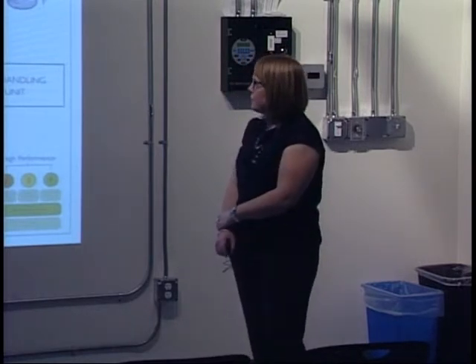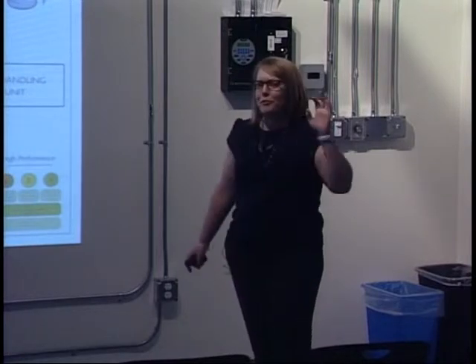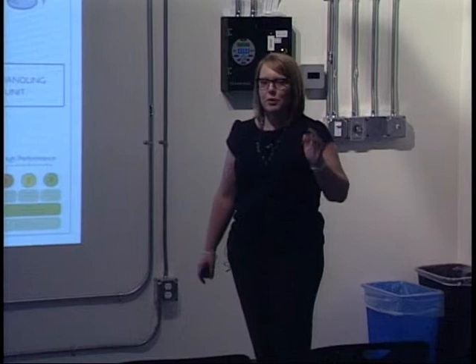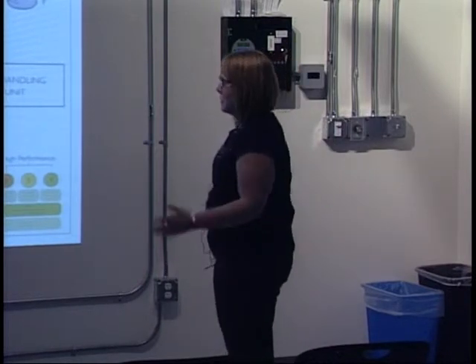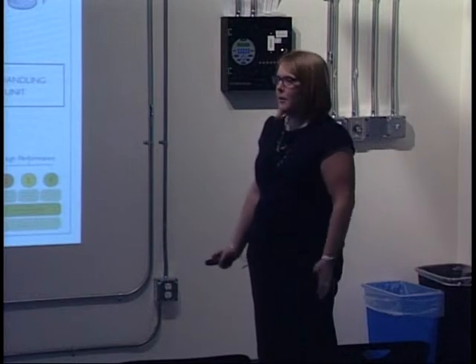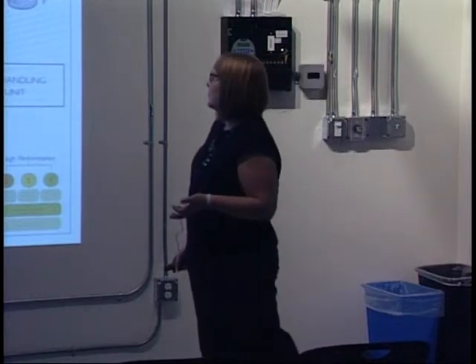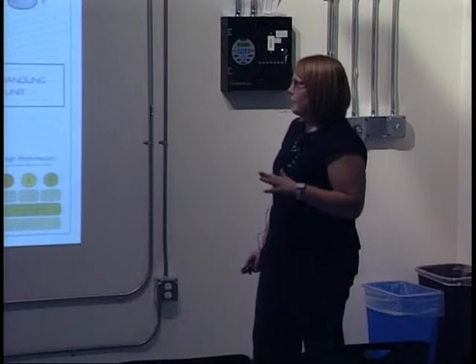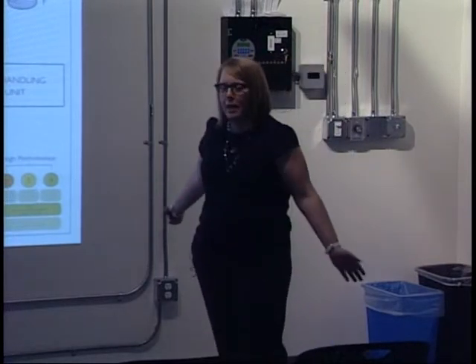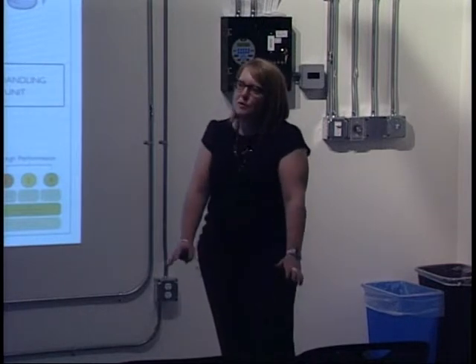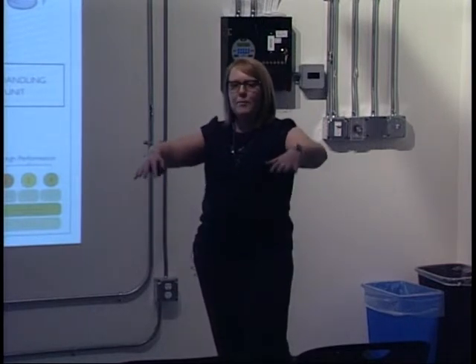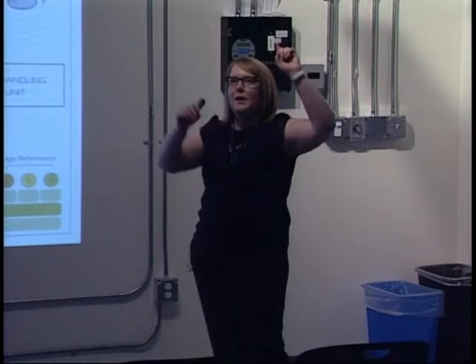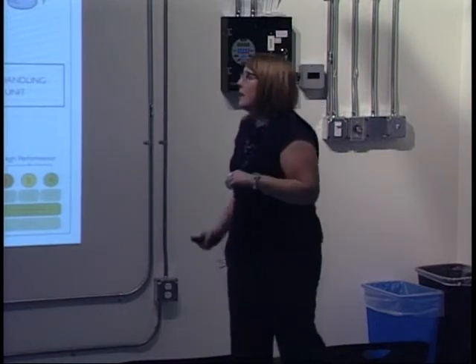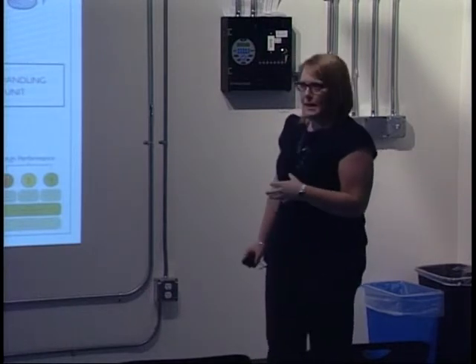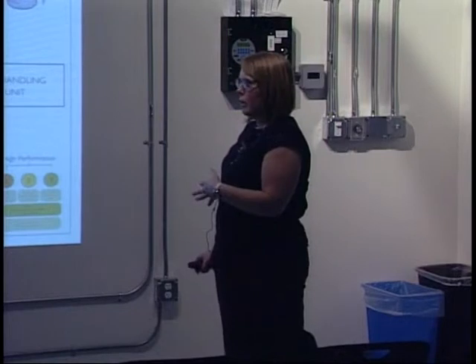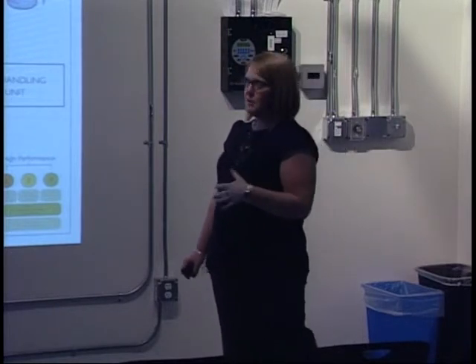How many of you are familiar with displacement ventilation? I'm going to talk a little bit about what that is and talk about the research that's gone into validating this as a good source of ventilation for hospitals. Essentially at the core of the concept is that the supply air is supplied low in the space, and it's using the natural piston effect of the air heating up and it moves up through the space, evacuating the air high in the space. And we worked really closely with Mazzetti and Stantec, who developed the initial work for this in healthcare and validated that it's a good method.